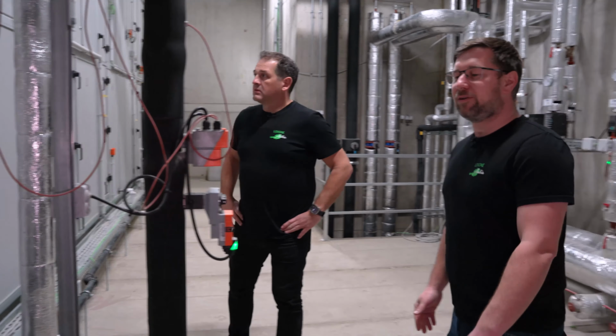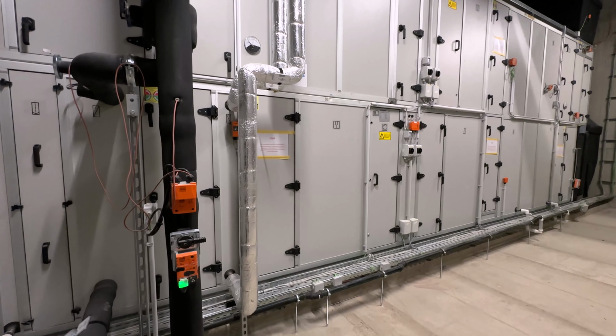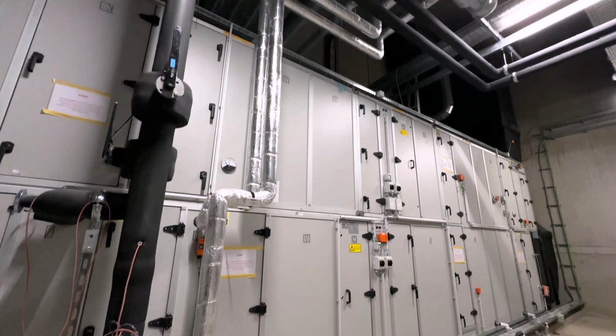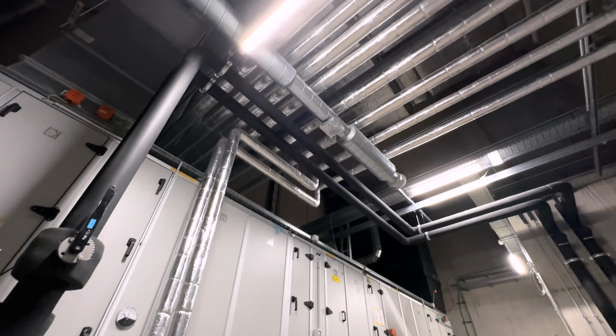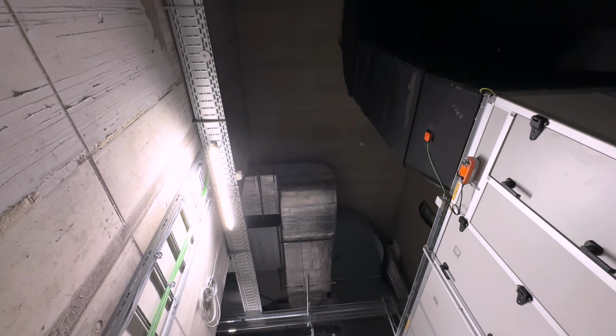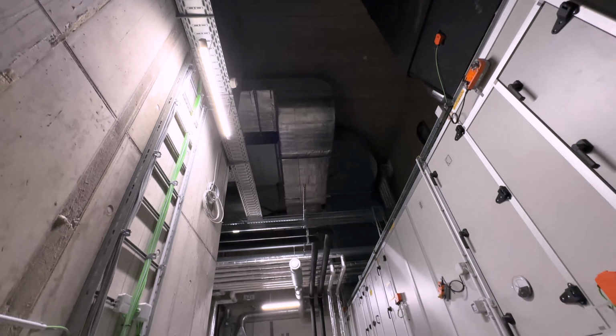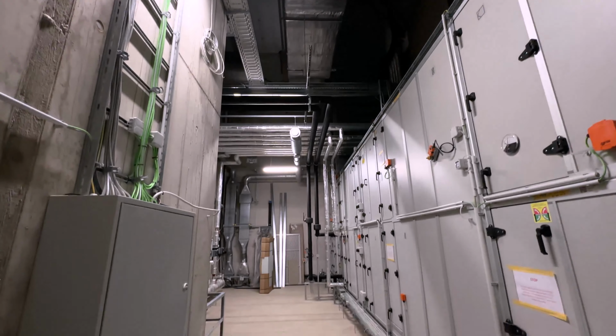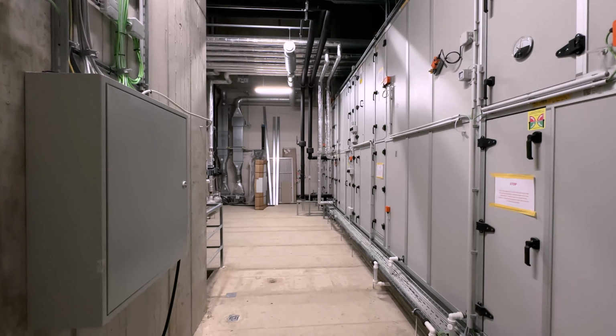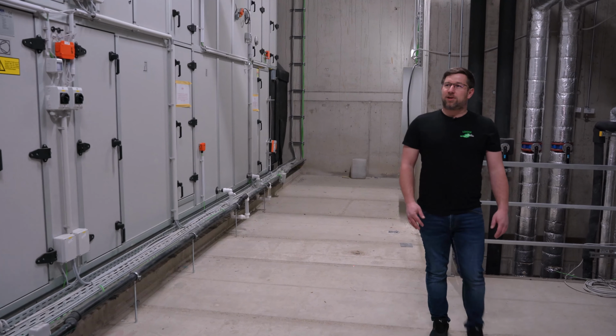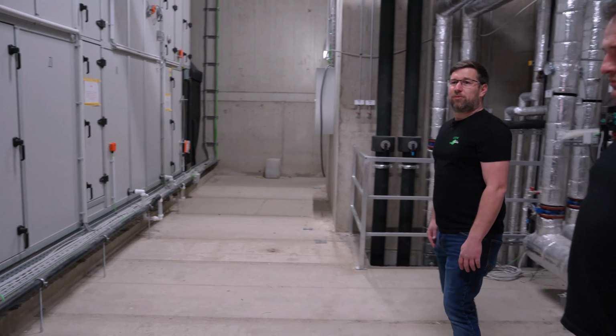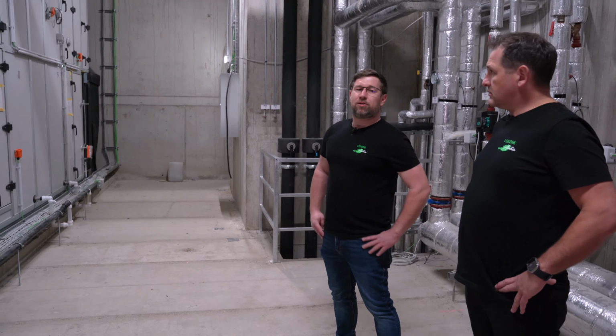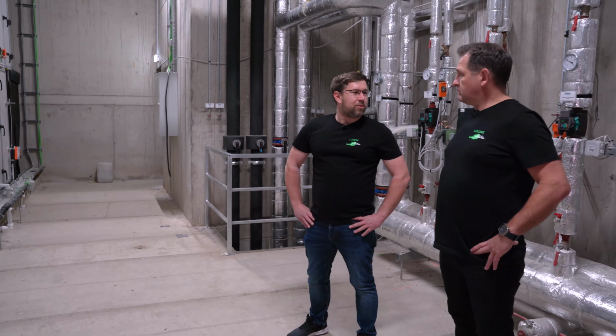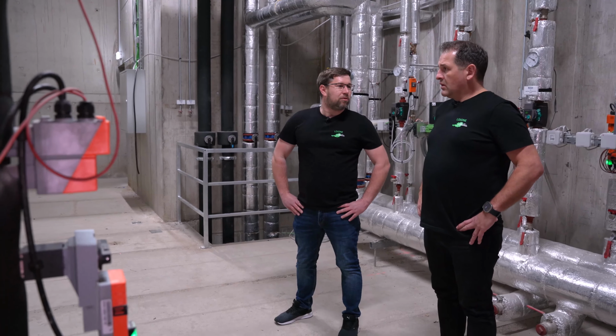And then the air gets taken off into the office, and up here is coming back from the office with the exhaust air, which is pumped out via the extract fans. It then goes through the cross heat exchanger again and is either released outside or is used again in recirculation mode. Recirculation mode is the mode that we actually run 95% of the day because more often than not, you don't need the fresh air as the CO2 levels are not high enough to need outside air.